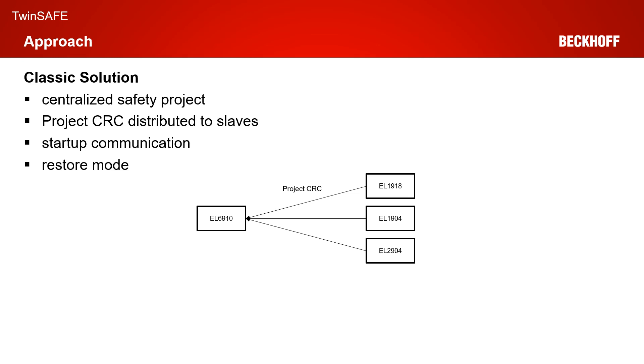When you are in restore mode, so you plug in a new EL6910 for example, and you download the safety project via our restore mode, then the EL6910 starts up. At startup, it asks for the safety project CRC of the yellow components. And if they answer correctly, the EL6910 safety project can start as if the EL6910 has never been changed.